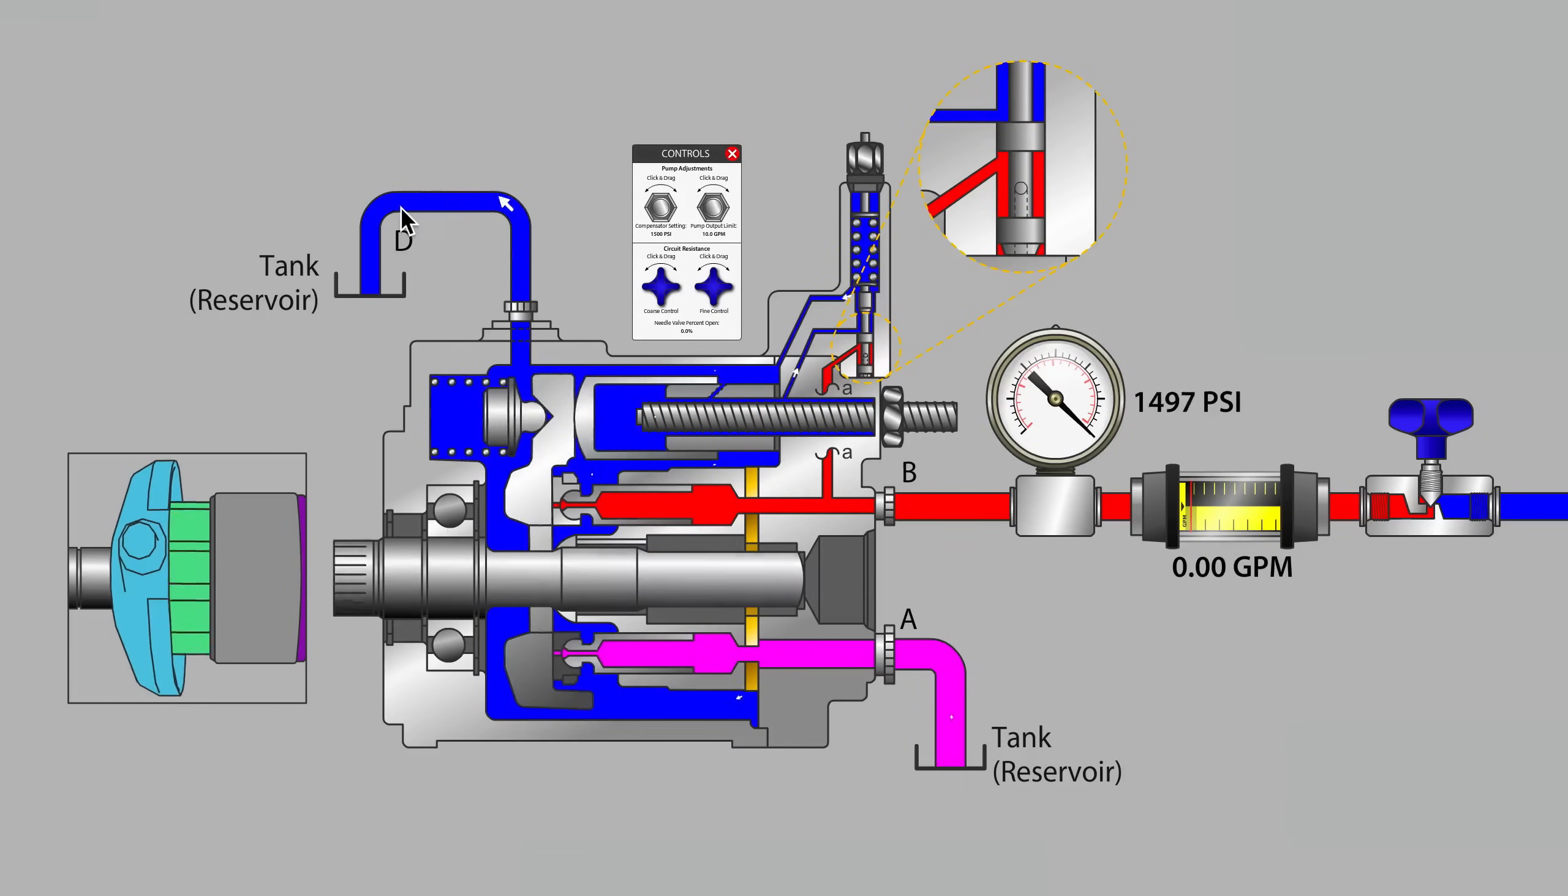So it's not uncommon to see 10% of the maximum displacement of pump present on the case drain line when we're at maximum pressure.